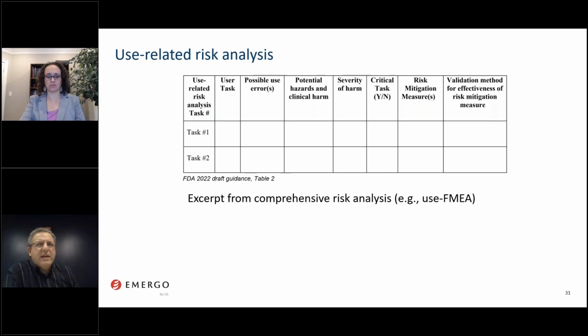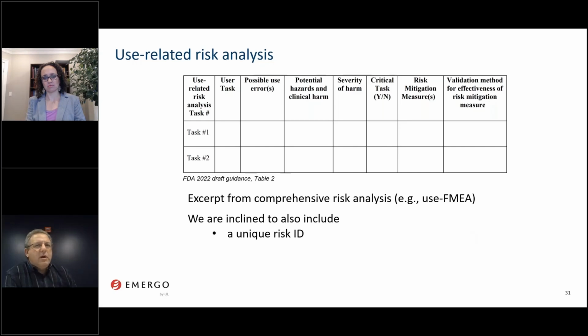So how might we approach documenting a use-related risk analysis? Well, while the agency has shown here what minimum information related to use-related risk analysis they would like included with your submission, our team would be inclined to add some additional information. So for example, a unique risk ID for each line item. Now this might be the same as the task number shown above in the table, but depending on the nature of your device and how you conduct your analyses, you could have the same task actually listed multiple times and therefore perhaps have the same task number repeated throughout the table. So we usually like to specify a unique risk ID for each line item in the URRA that effectively ties each line item back to a unique risk, say in the comprehensive use-related risk analysis.